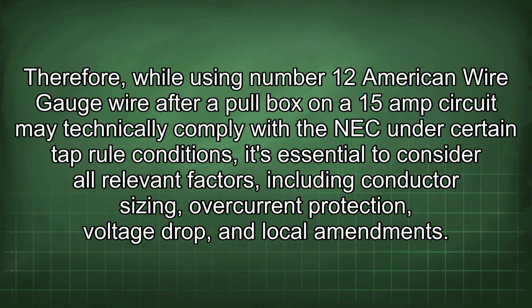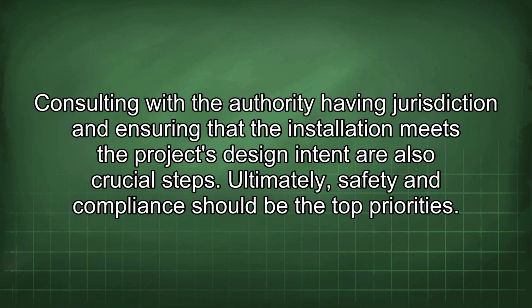Therefore, while using number 12 American wire gauge wire after a pull box on a 15 amp circuit may technically comply with the NEC under certain tap rule conditions, it's essential to consider all relevant factors, including conductor sizing, overcurrent protection, voltage drop, and local amendments. Consulting with the authority having jurisdiction and ensuring that the installation meets the project's design intent are also crucial steps. Ultimately, safety and compliance should be the top priorities.